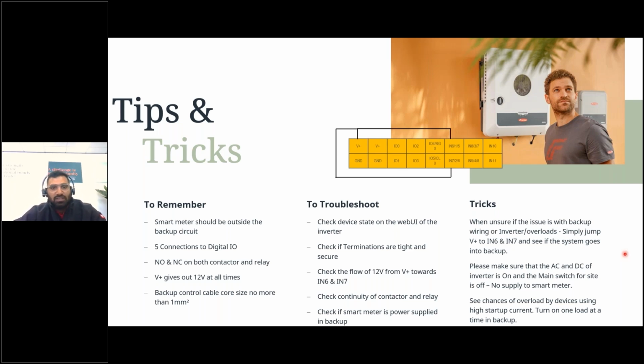And if you still don't have the inverter working, even with this little jumper test, when you jumper directly from V+ to IN6 and IN7, please consider the possibility of overload as a reason why the system hasn't gone into backup. Another scenario, which is very rare, is that you try to plug in the cable and maybe damage the terminals. You could reassign and use IN8 and IN9 instead of IN6 and IN7. It is not necessary that you stick to IN6 and IN7. You can always use another input terminal and see if it works.